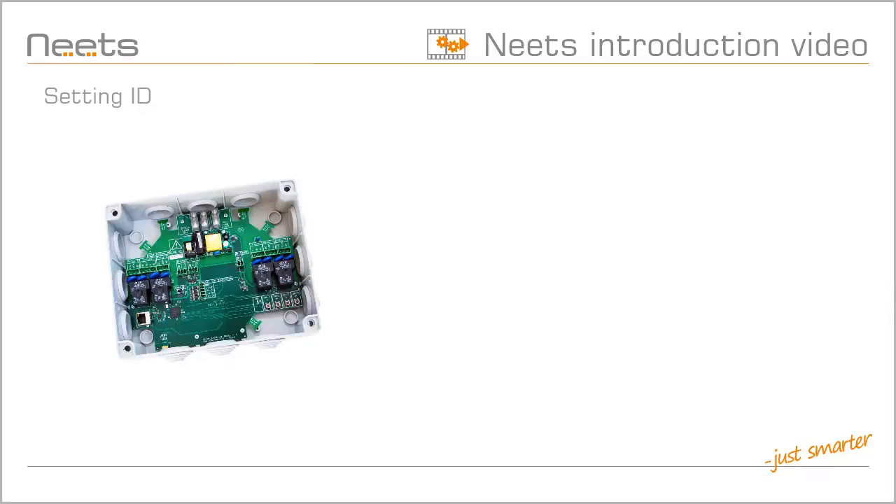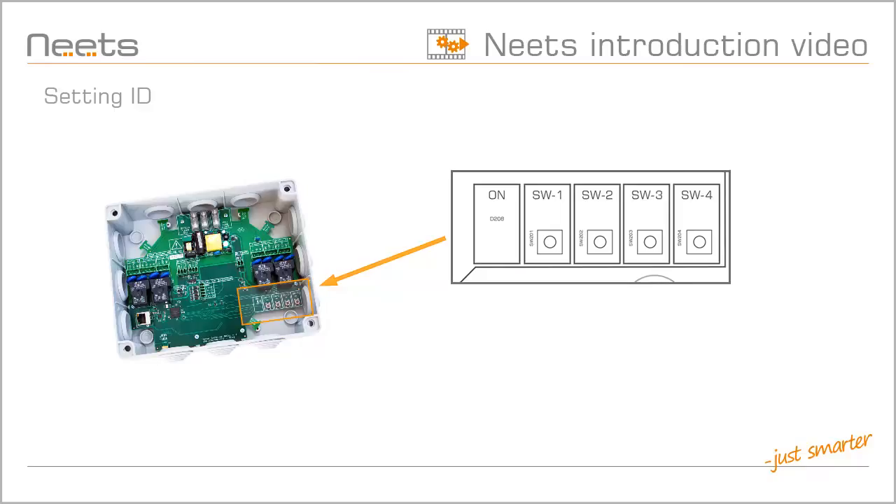You would need to set a different ID on each of the Switching Relays. The Neets Switching Relay ID can be changed by RS-232, network, or the test buttons. Let me demonstrate how it is done. When connecting the power to the Switching Relay, you will see that the power LED is blue and one of the relay lights is on. This is the current ID.